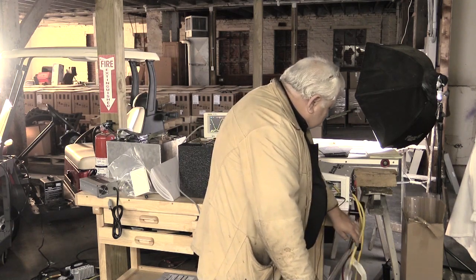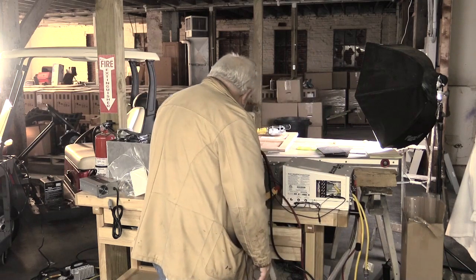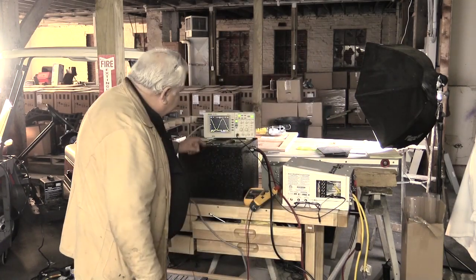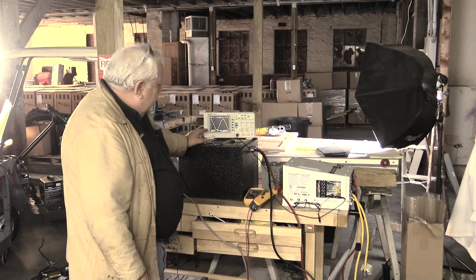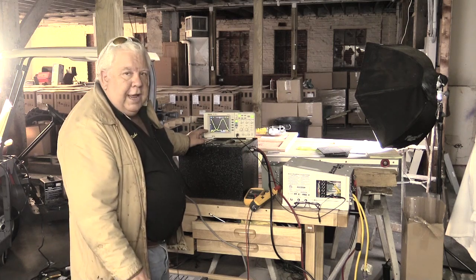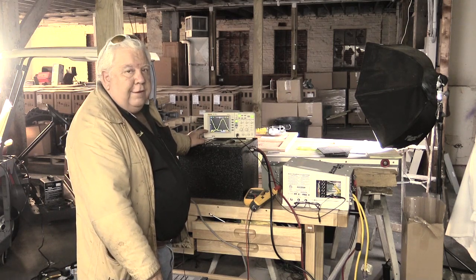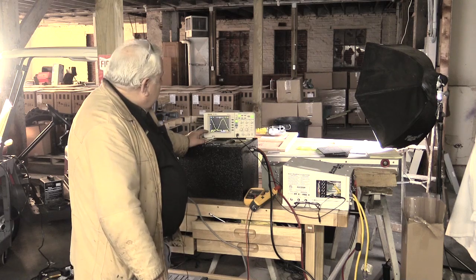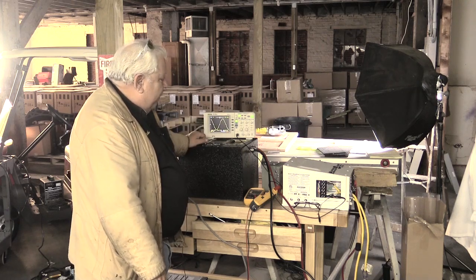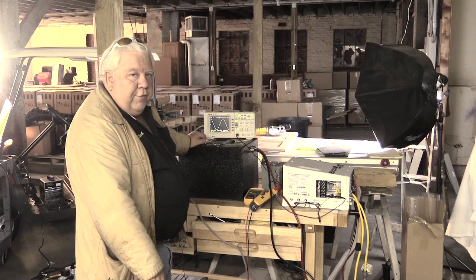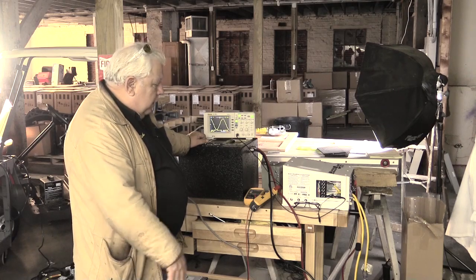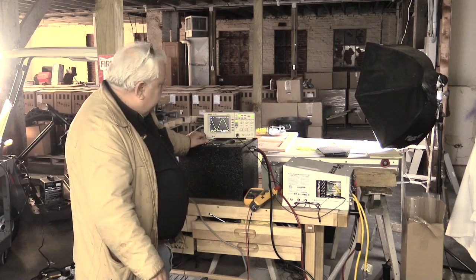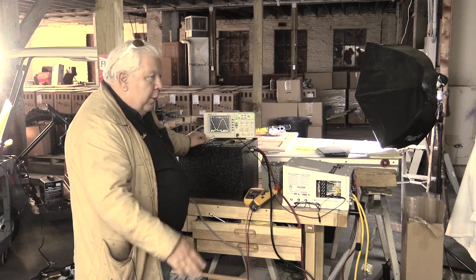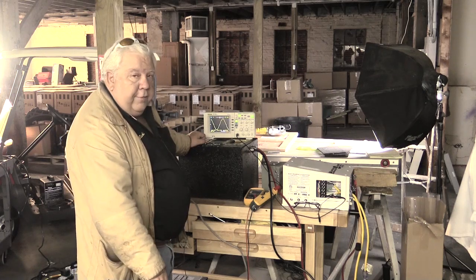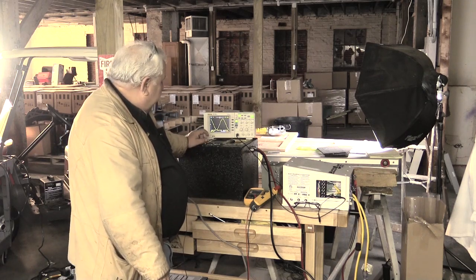I'm going to disconnect my power, and here we still have a waveform. In fact, you can't notice it switch over. It does so in less than 16 milliseconds, which coincidentally is about one waveform. So even if you have a computer hooked up to this thing, when you lose power, it picks up off the battery with a little transfer relay inside there, very adroitly.